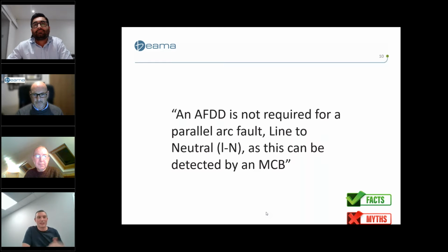Okay, yeah. Well, AFDDs are designed to operate where high impedance faults occur, for example, damaged insulation between line and neutral. And that's versus MCBs, which actually require low impedance fault conditions to operate, for example, a short circuit. It's really dependent on the magnitude of the arc fault current. The fault current required to operate an MCB would be much higher than an arc fault current, for example, which can cause ignition of combustible material.